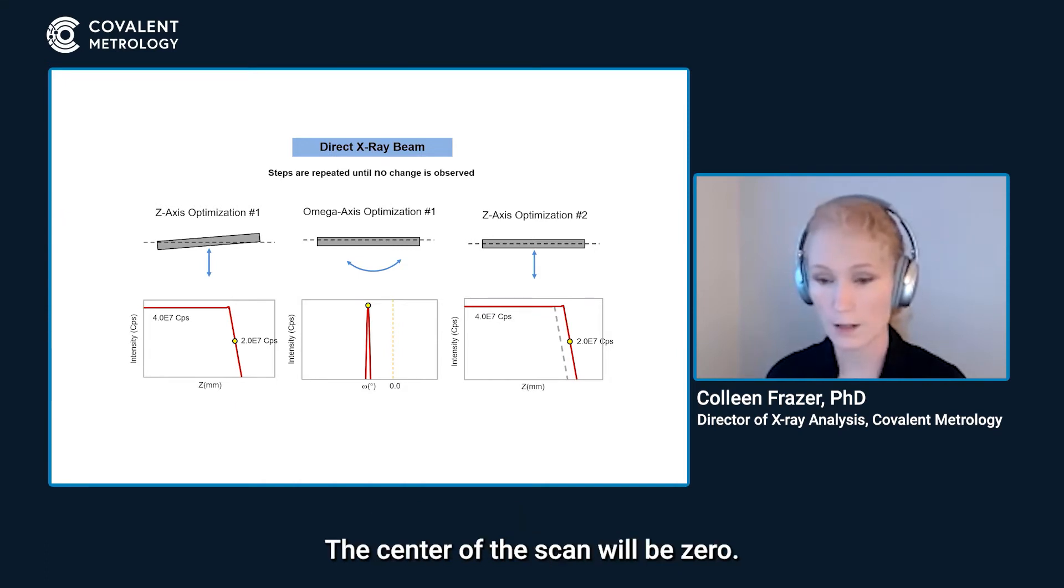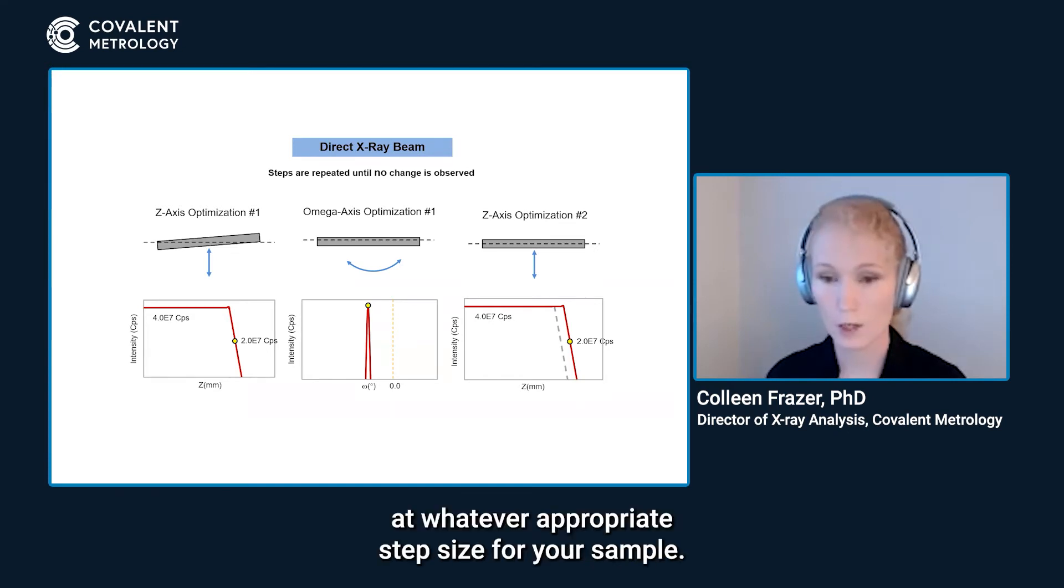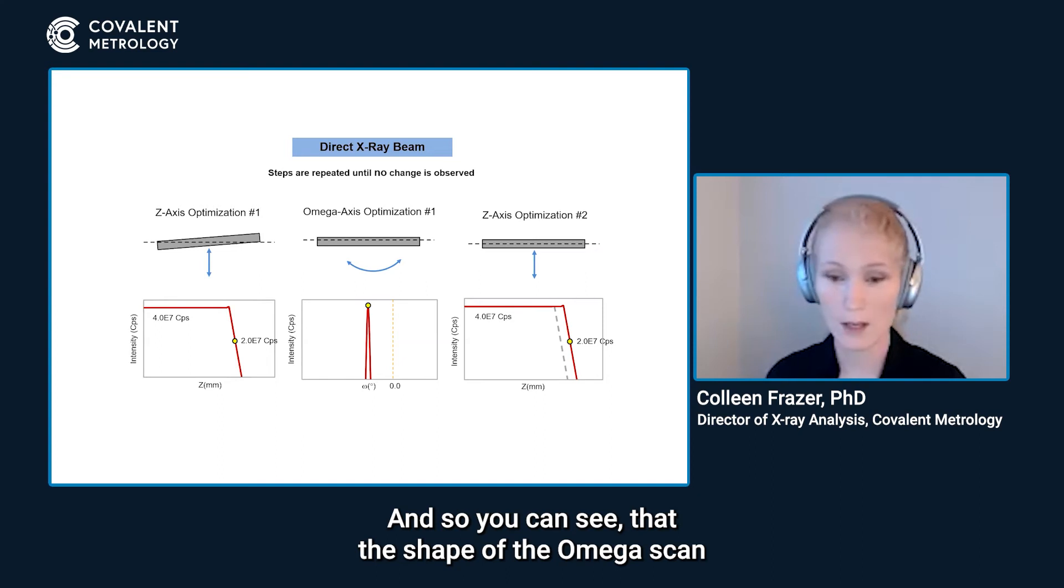The center of the scan will be zero, rock omega at whatever appropriate step size for your sample and you can see the plot that we have here. We find the maximum intensity and then we use offsets to move that to zero in this case. This particular sample was very flat, not a lot of curvature to it and so you can see that the shape of the omega scan is very sharp and fairly narrow.